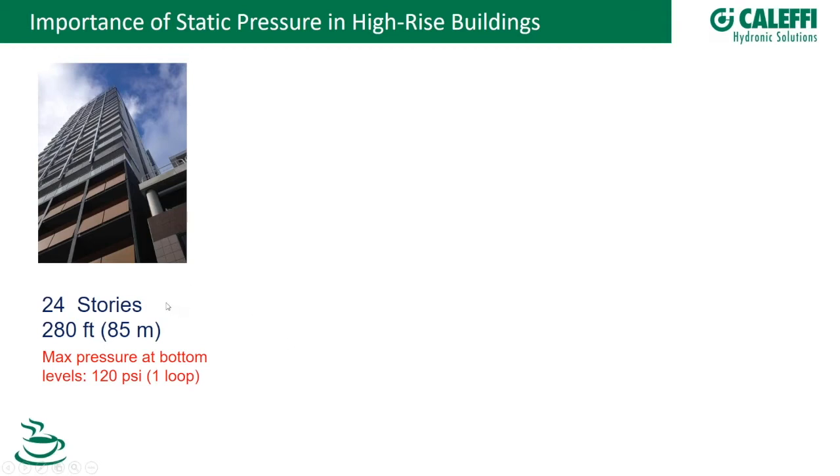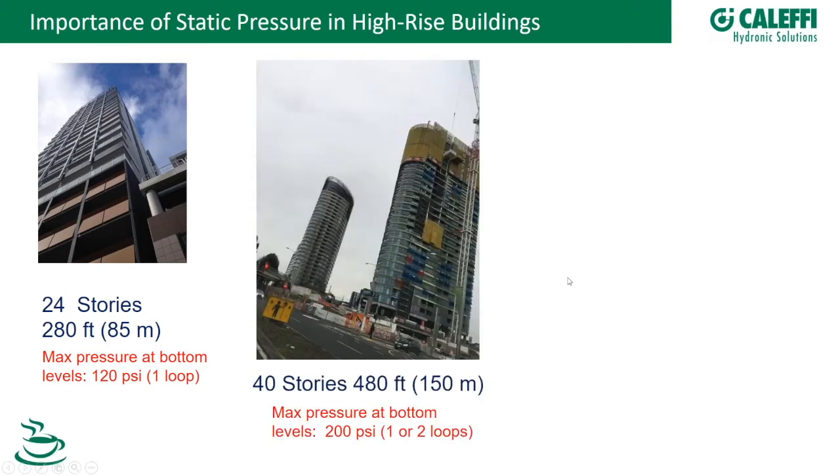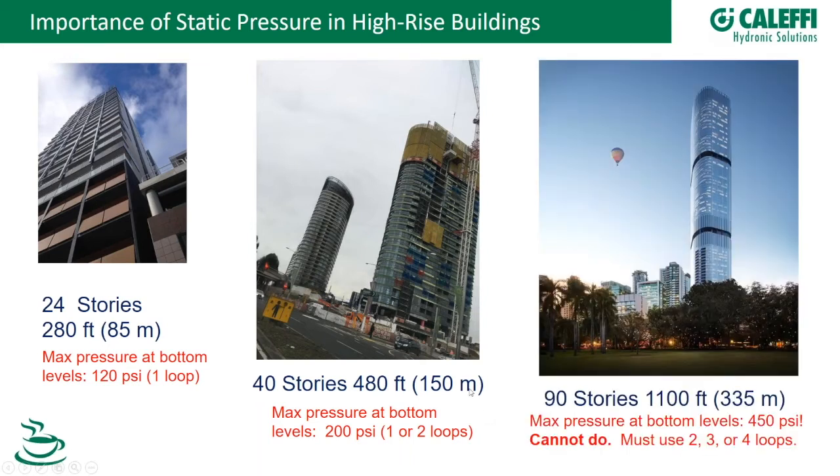For a 24-story building with a maximum height of 280 feet and maximum pressure at the bottom of 120 PSI, one recirculation loop for hot water is normally enough. For a 40-story building at 480 feet, the maximum pressure at the bottom reaches 200 PSI — making it quite tricky, and requiring consideration of one or two loops. For a 90-story, 1,100-foot building, it's nearly impossible to manage bottom-level pressure, so the system must be split into two, three, or even four loops.